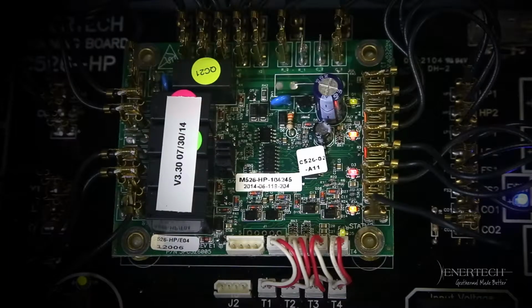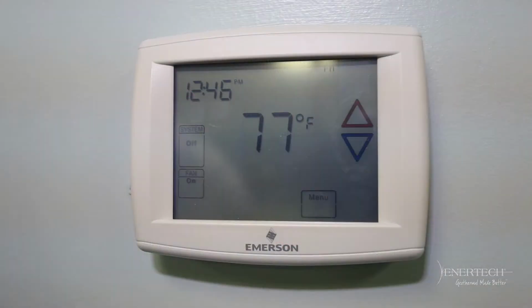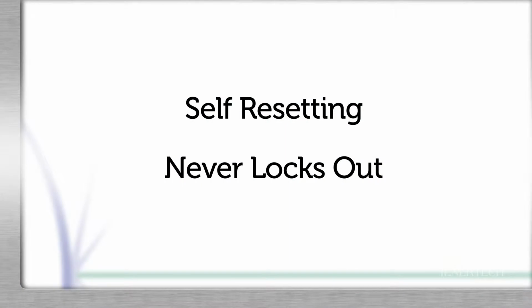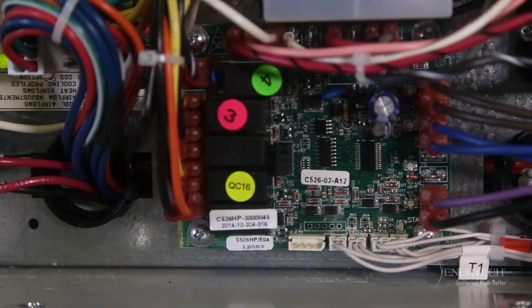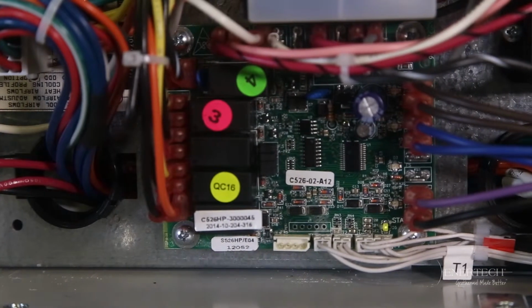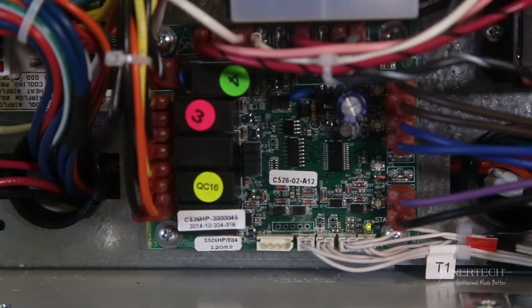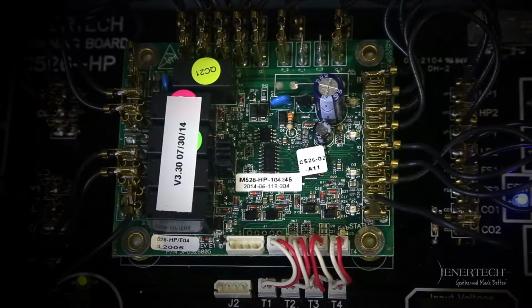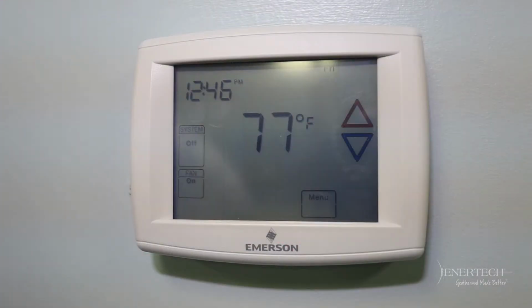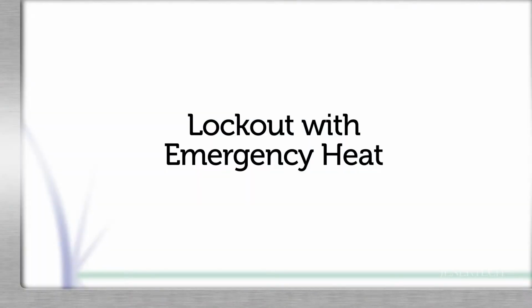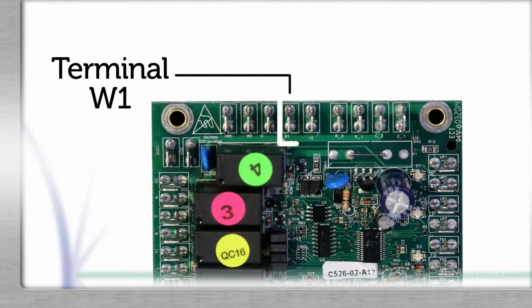During lockout, all 4 fault LEDs will flash, HP, LP, FS, and CO, and the thermostat call for service indicator will be illuminated. This feature is self-resetting and never retries or locks out. If voltage returns to normal range, normal operation will resume if or when the ASC period is over. When normal operation is restored, the 4 fault LEDs will stop flashing and the call for service indicator will turn off. While in lockout mode, if the thermostat is calling for auxiliary heat on W1, emergency heat mode will energize. W2 is energized 2 minutes after W1 is energized.